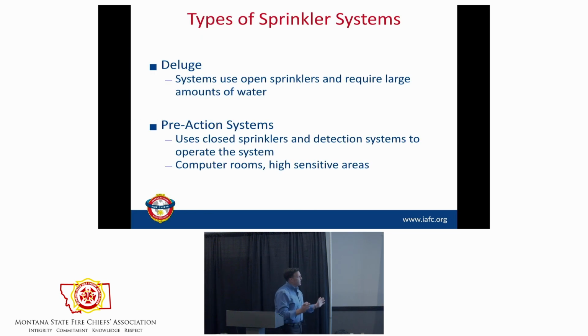So we can have all these other things. Deluge if we needed, open sprinklers, perimeter protection. If you ever see a hotel on the airport terminal, and there's planes that can park near it, it probably has deluge sprinklers on the exterior. If there's an event, it can just shower the building. Pre-action systems are a mix of dry and wet.